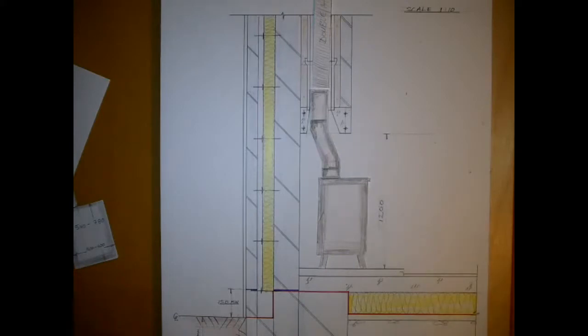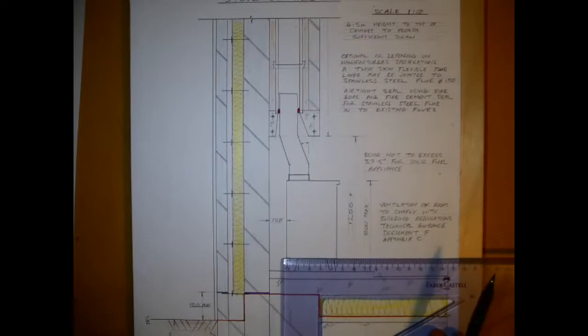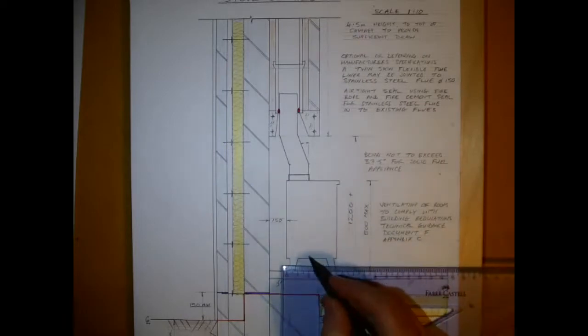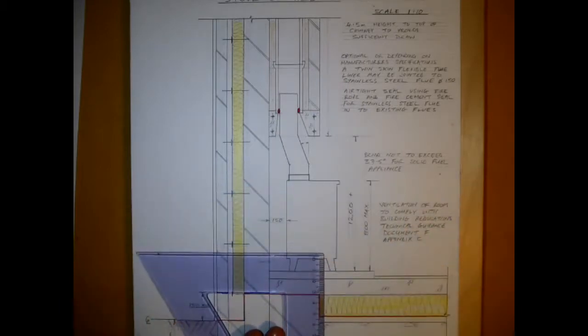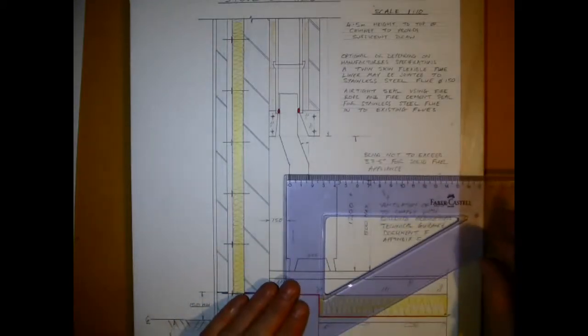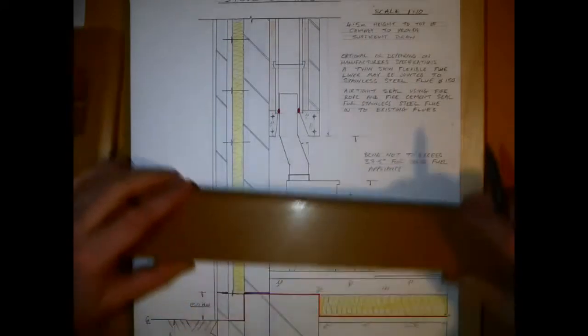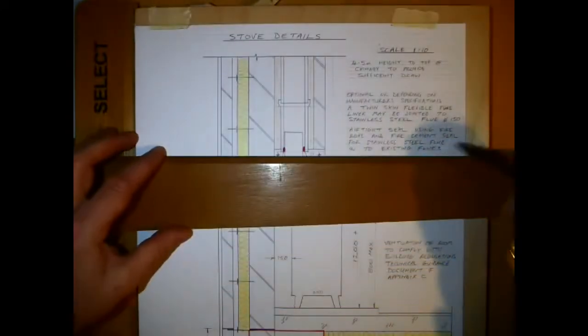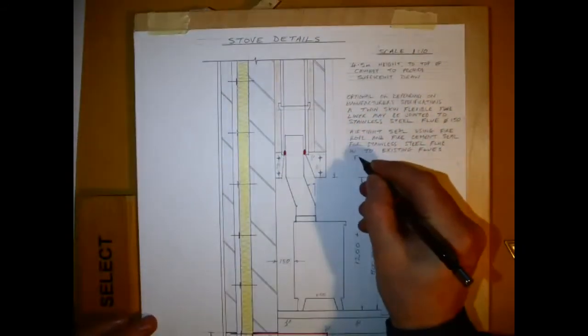And that should show you or explain to you how you might go about putting the stove in, which is not really any different to our drawing for the fireplace on the ground floor. I'm sticking in a few dimensions here, and there's a few details that you might want to follow that are on this here. Things like ventilation into the room. The angle of the bend should not exceed 37.5 degrees. Where you might see 45-degree bends used is the only thing maybe to watch out for. You wouldn't use a flexible bend in that, you would use stainless steel.